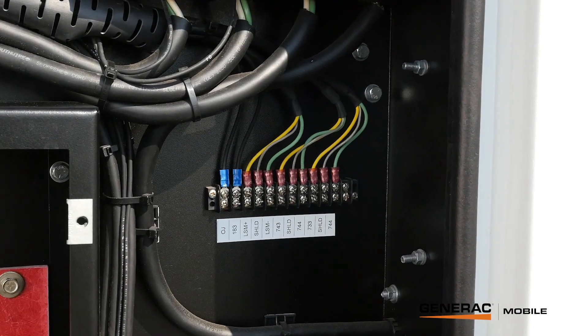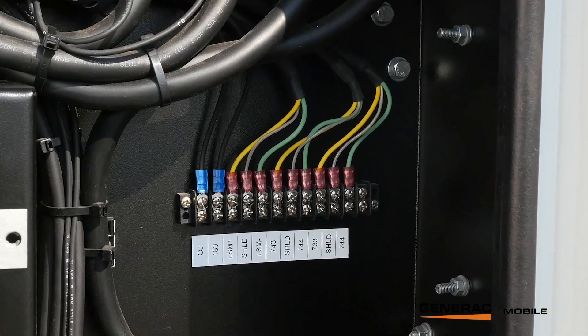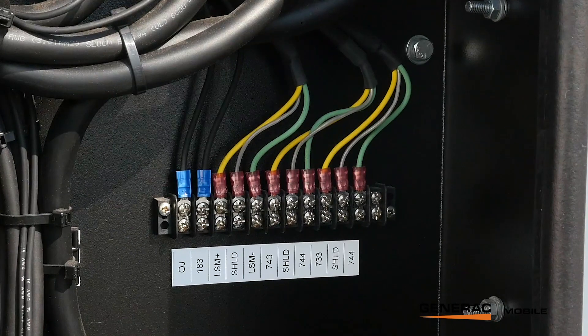The six colored wires on the far right are your standard CAN connection between any COMAP or similar MGG 450 units. The three colored wires to the far left are for analog load sharing with a third-party controller such as Deepsea or DEIF. The two black wires on the far left of the terminal block are for a remote start connection.